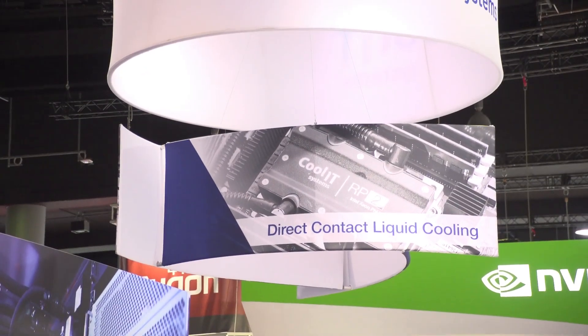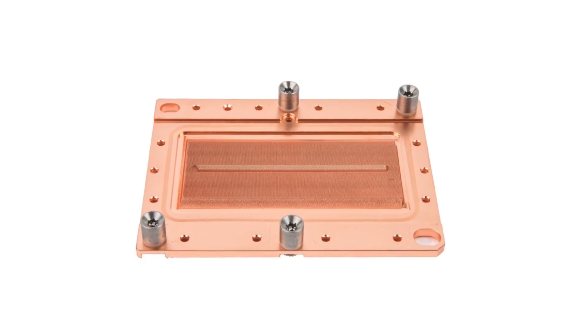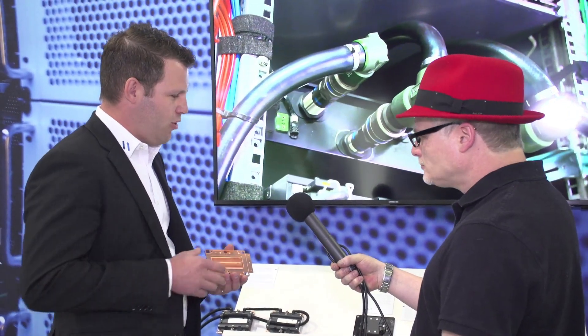What are you guys showcasing this week at ISC? We're showcasing quite a bit. For CoolIT, it's always a modular story, so we start usually at our cold plates. We sponsor a bunch of different cold plates with various partners. Today we're showing the Socket P Intel Skylake cold plates, a new cold plate for AMD EPYC CPUs, as well as the NVIDIA V100. An important part of the story is that all the cold plates we sell and manufacture have split flow technology inside — it's a CoolIT patented technology. All the various cold plates you see today have the same geometry inside, making it an extremely high performing cold plate used across all our products.